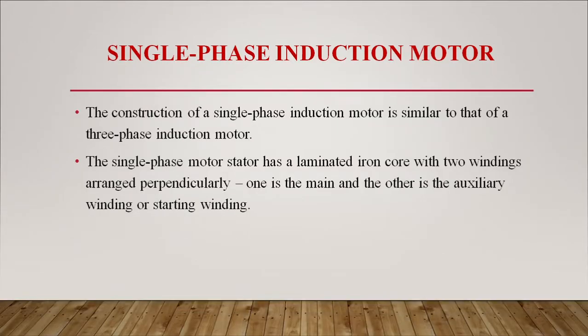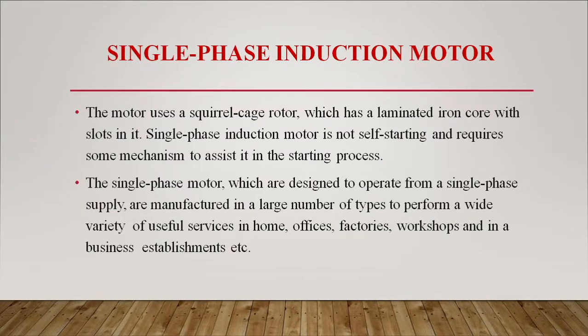Construction of a single phase induction motor is similar to that of a three phase induction motor. The stator has a laminated iron core with two windings arranged perpendicularly — one is the main winding and another is the auxiliary or starting winding. The motor uses a squirrel cage rotor with a laminated iron core with slots. A single phase induction motor is not self-starting and requires some mechanism to assist it in the starting process.